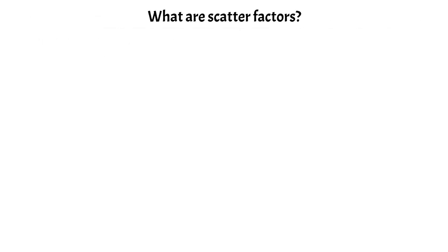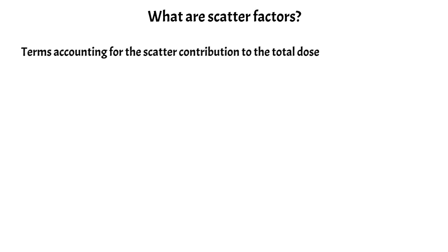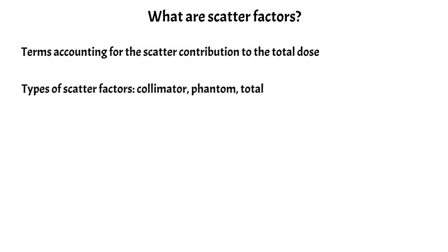We can start with what a scatter factor actually is. It's a term that accounts for the scatter contribution to the total dose. As mentioned in a previous video, the total dose in a hand calc can be broken into three parts: the contribution from primary dose, and contributions from scatter — both from the collimator and from the phantom. Because of that, there are really three scatter factors we consider in a hand calculation: the collimator scatter, the phantom scatter, and then the previous two can be multiplied together to form the total scatter factor.